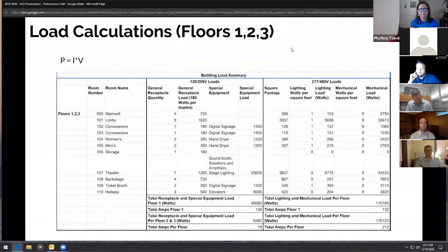We used the receptacle layout and counted receptacles to input the quantity of receptacles in our load calculations, and multiplied that by 180 watts. Then we added the watts for the special equipment pointed out in the last slide and used the equation P equals I times V, rearranged to calculate for the current, where P is power in watts and V is voltage, either 120-208 volts for receptacles or 277-480 volts for lighting. The reason for these different voltages is that for large loads we want decreased current so we can make panels and wires smaller. We calculated the current, I, in amps, then divided by 3 because we went with a 3-phase electrical system.